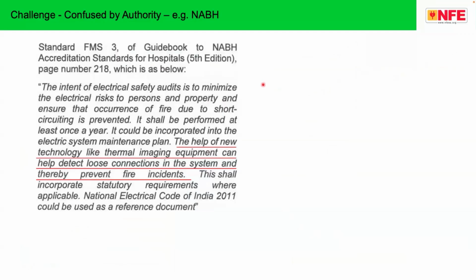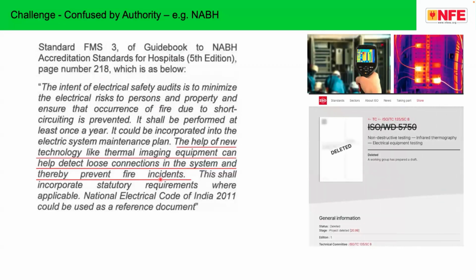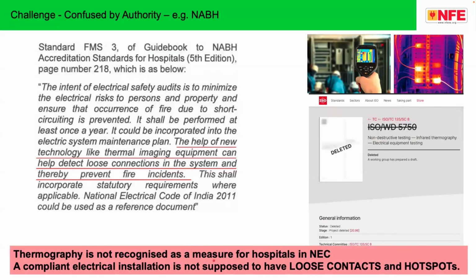Okay. Thank you. Now, challenges: confusion created by authority. A lot of hospitals nowadays are NABH accredited. Unfortunately, the last edition of NABH has included one line: the help of new technology like thermal imaging can detect loose connections in the system and thereby prevent a fire incident. Thermal imaging or thermography is not recognized as an electrical safety measure at all.